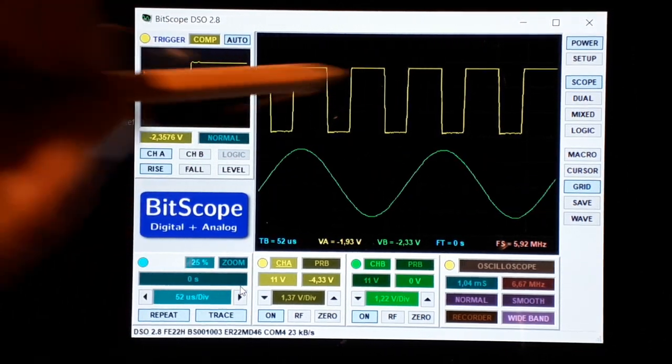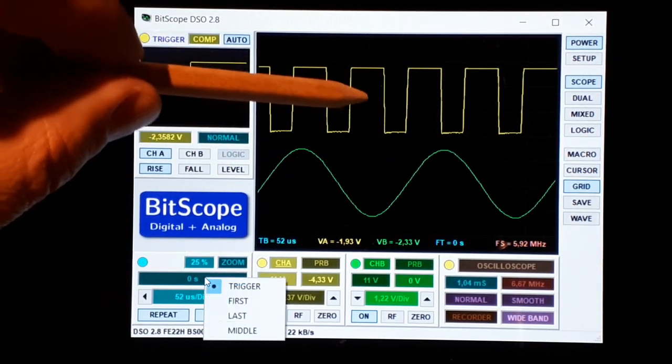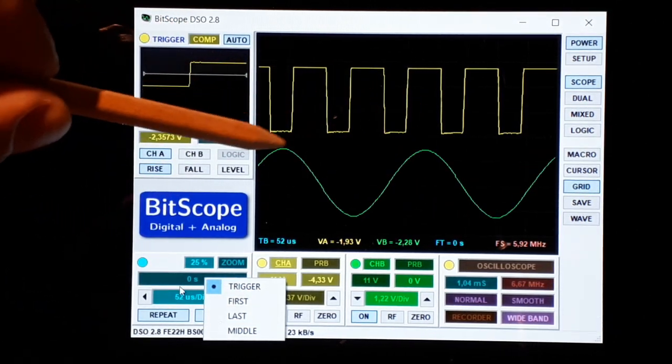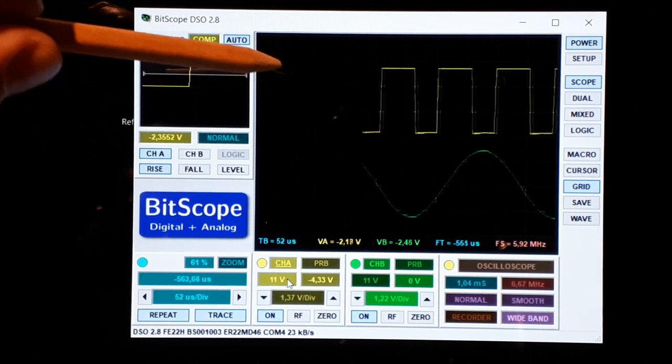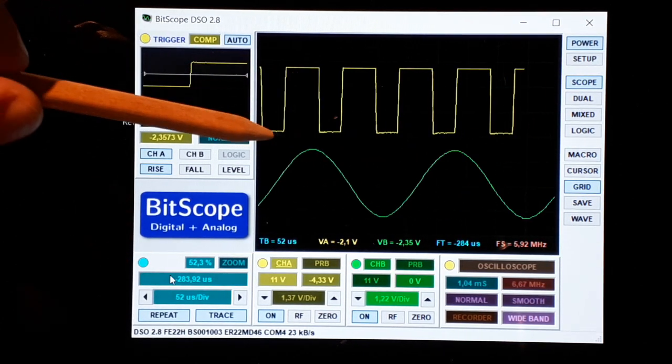Then you have more things than the trigger. Here is the trigger point, so you have the trigger point but also you have some more information stored before that. So you could analyze what happened before the trigger point.